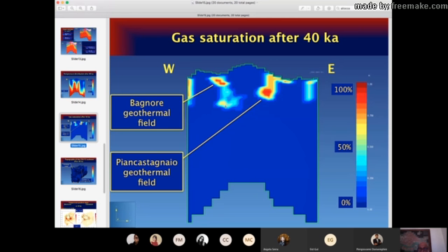And it is through condensation of the vapor as it goes across the turbine that generates electricity that I can recover this enthalpy and produce electric energy. Therefore, what matters is not so much the pressure that the fluid has, as how much vapor is contained in this fluid. And what you usually do is separate the water from the vapor, and you run through the turbine only the vapor.